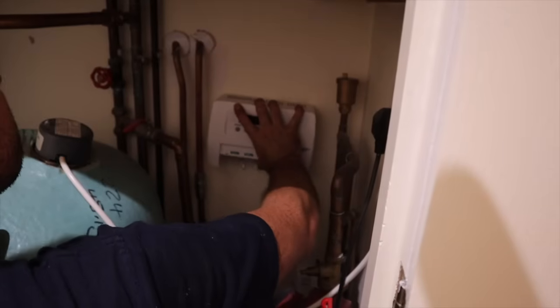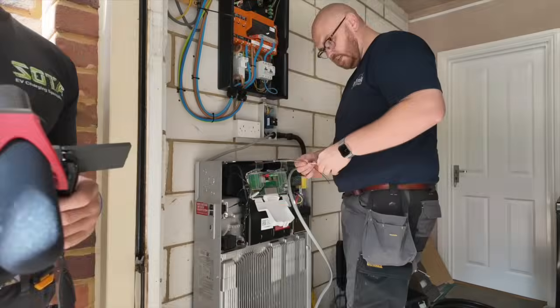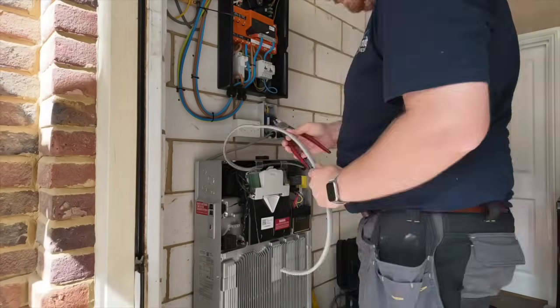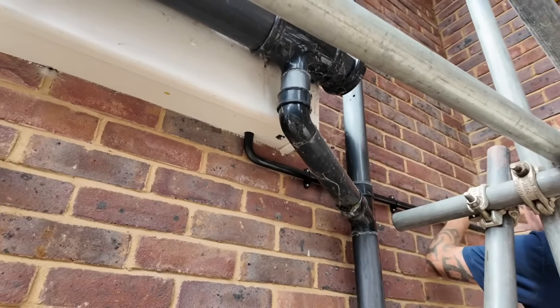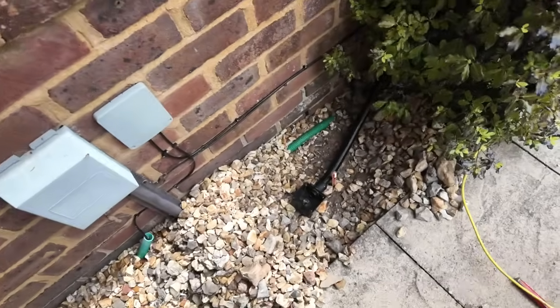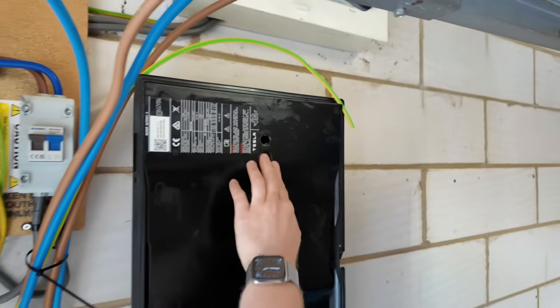On this job they are also having a solar iBoost installed. What that does is take the excess energy generated from the solar and use it to heat up the hot water in the cylinder — maximizing the use of solar-generated energy and minimizing as much exported energy as possible. They've also conduited the earth cable at high level and routed it up through the porch area rather than clipping it around the front of the house, then conduited back down to the earth spike.